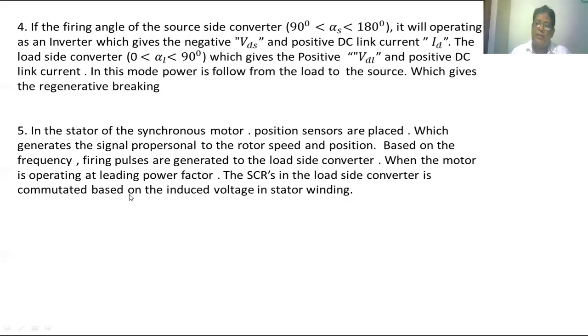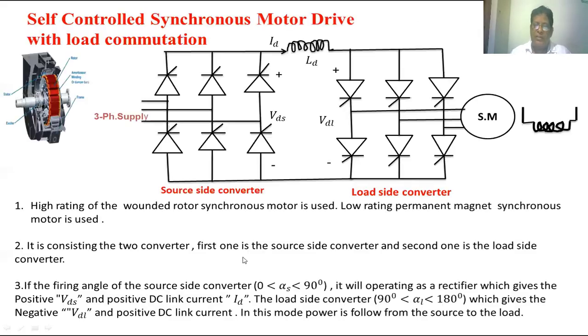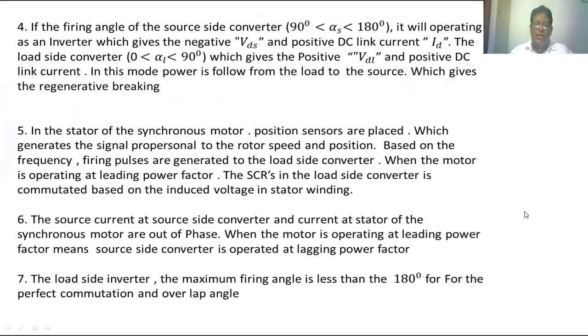How we are going to generate a firing pulse to the load side converter: in the stator we keep a position sensor. The position sensor gives information about the frequency as well as the phase angle of the induced voltage in the stator winding. Based upon that frequency and phase angle, we apply the firing pulse to the load side converter. The maximum firing angle of the load side inverter is limited to take into consideration the commutation as well as the overlap angle.